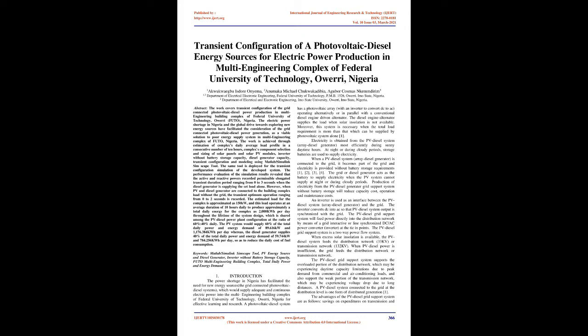The PV system would supply 60% of the total daily power and energy demand of 89.616 kilowatts and 1,176.384 kilowatt-hour per day, whereas the diesel generator supplies 40% of the total daily power and energy demand of 59.744 kilowatts and 784.256 kilowatt-hour per day, so as to reduce the daily cost of fuel consumption.